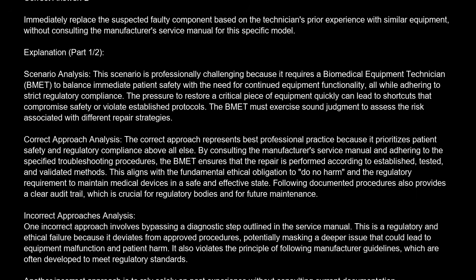This aligns with the fundamental ethical obligation to do no harm and the regulatory requirement to maintain medical devices in a safe and effective state. Following documented procedures also provides a clear audit trail, which is crucial for regulatory bodies and for future maintenance. Incorrect approaches analysis. One incorrect approach involves bypassing a diagnostic step outlined in the service manual. This is a regulatory and ethical failure because it deviates from approved procedures, potentially masking a deeper issue that could lead to equipment malfunction and patient harm. It also violates the principle of following manufacturer guidelines, which are often developed to meet regulatory standards.